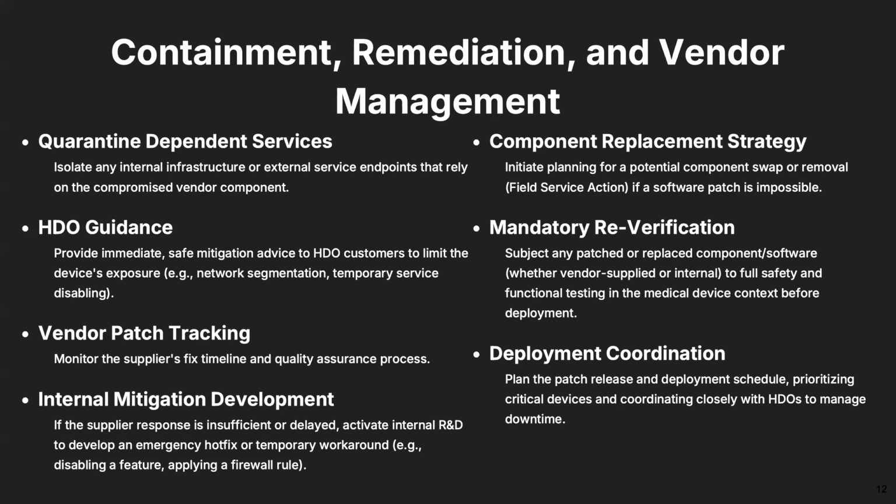And the FDA has repeatedly, and you can check their frequently asked questions, talked about how that cycle should not necessarily inhibit when an update or a solution gets pushed, but you need to somehow demonstrate from a documentation perspective that it is safe and you are able to make a software update. And then obviously coordinating that with clinical operations, the user of the device, whatever your ongoing support cadence is, is really important.